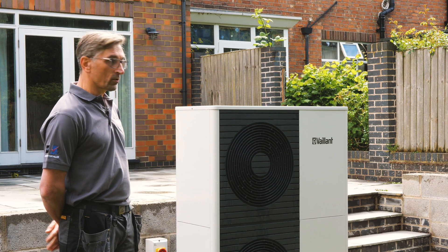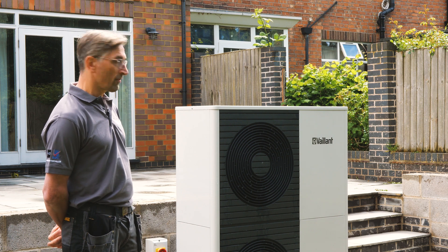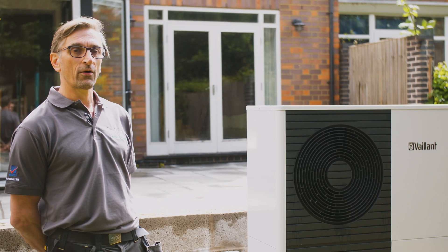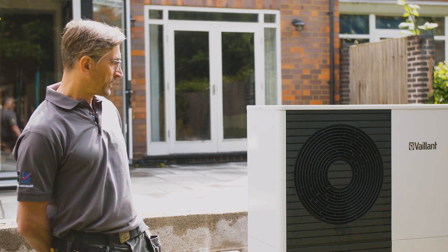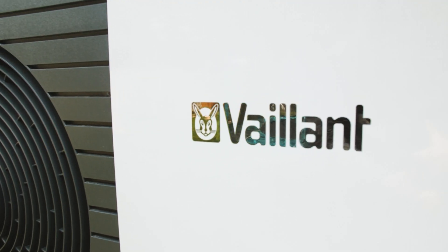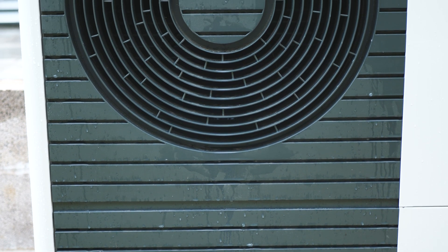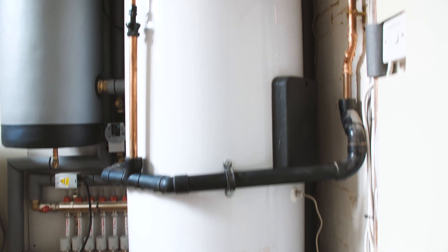On the outside we have the Vaillant air source heat pump — it's a Vaillant aroTHERM plus 12 kilowatt — and this is what generates the heat to give you heating and hot water within the home. It flows air across the back, pulling it through these fans, takes a few degrees Celsius off the air into refrigerant, then compresses that refrigerant with the compressor, which increases the temperature, and then transfers that increased temperature to the water flowing within the home and into the hot water cylinder.